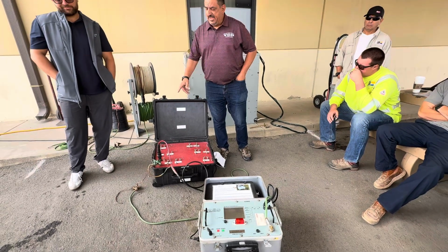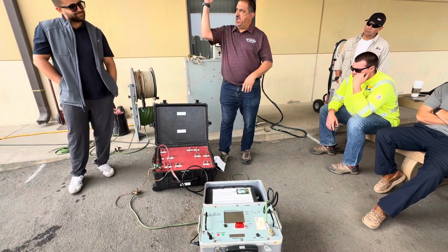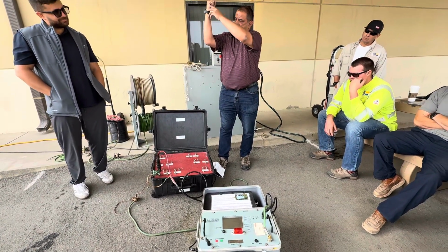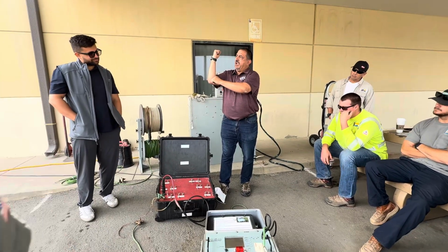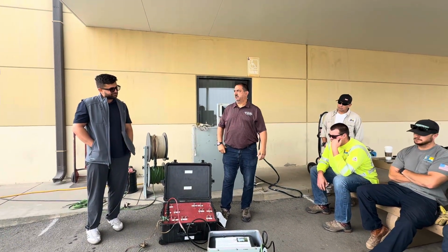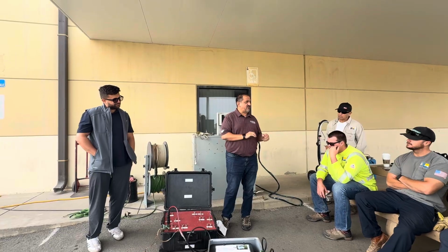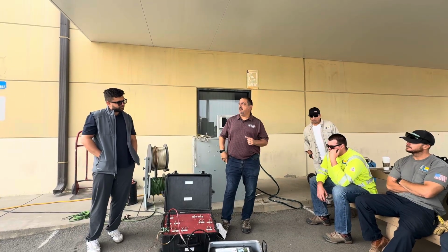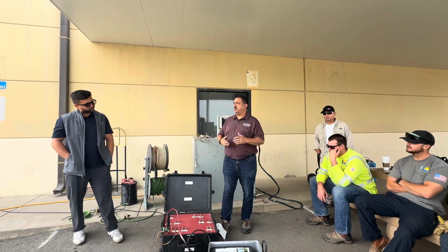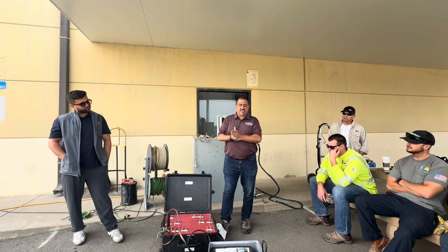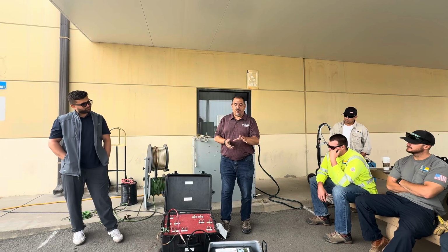Yeah. And ideally, for that return, if the elbow's here, where we're hooked up, ideally I want to be like 6 to 8 inches away on the neutral of the cable that we're testing. Now, I know all your neutrals are tied together, and that's one of the common questions: what difference does it make if all my neutrals are tied together? And the reason is you're going to get a better radar picture.